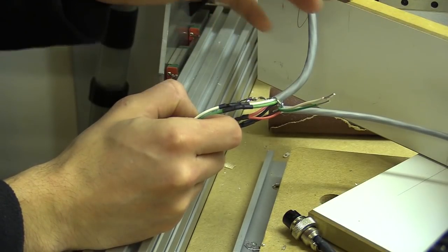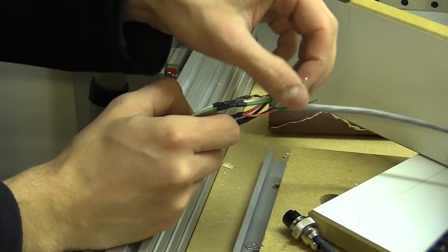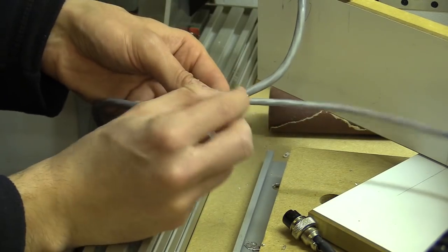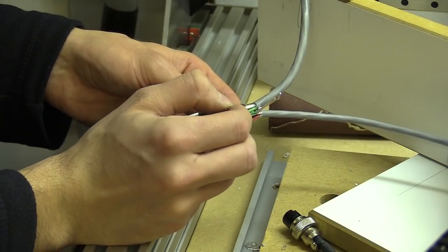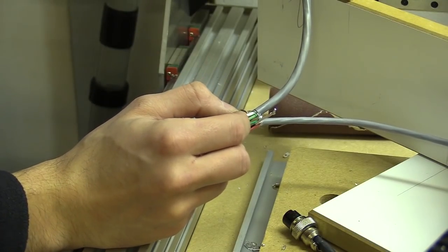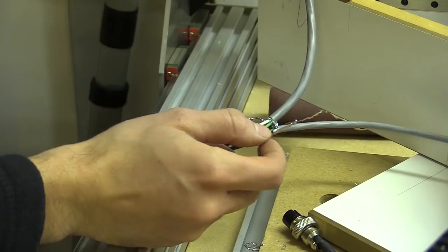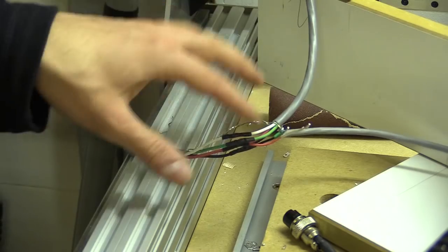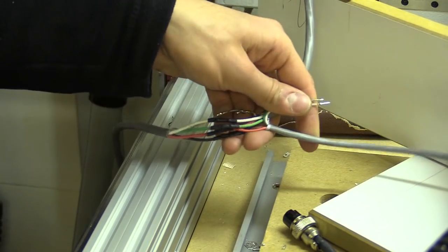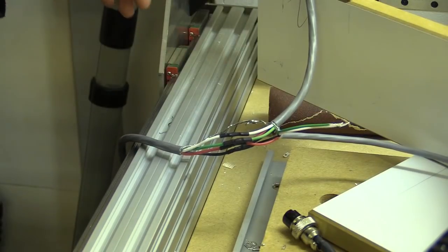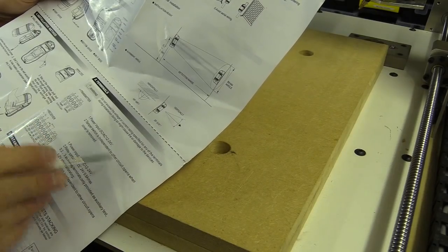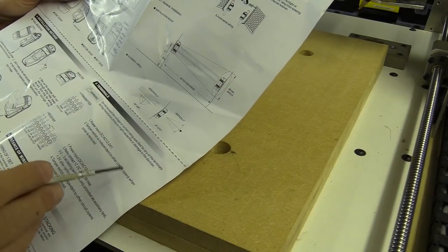I'm not sure how the tamper works. The tamper circuitry can be wired to prevent tampering with the transmitter or receiver. When the cover of either unit is taken off, a switch is released which can be used to signal or activate some other behavior. I could possibly even wire the signal wire through the tamper switch so removing the cover acts in the same way as breaking the beam, but that's overcomplicating so I'll ignore those terminals.